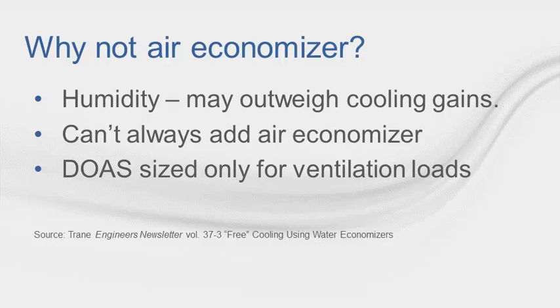Why would I use a waterside economizer when I can just put an economizer on my air handlers? A few reasons include the following. Tight humidity requirements may negate the efficiency gains of an air-side economizer. If the air is cool but humid, it may cost more to dehumidify than is gained by the reduction in cooling, or if the air is dry, humidification loads might increase.